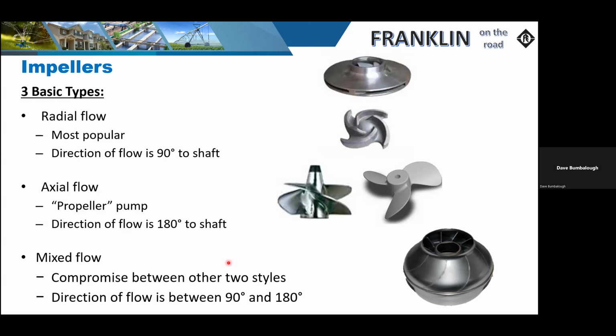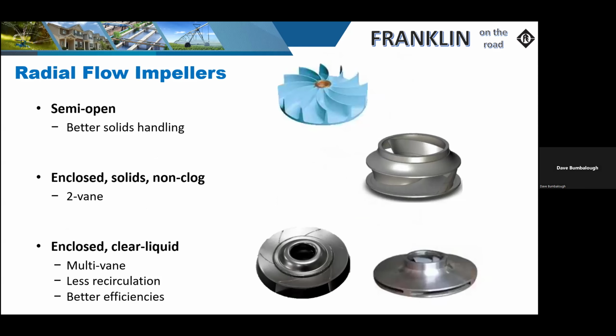There are mixed flow designs, which you'll see in some of the larger pumps, such as turbines and a lot of the bigger volume type pumps, especially if we're trying to increase flow. Those are the best designed for that application. And the efficiencies do move up quite a bit with those mixed flows. Now, when you're talking about radial pumps, there are different designs inside that arena.